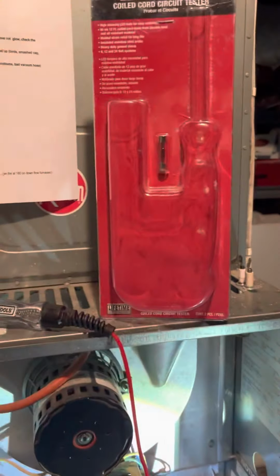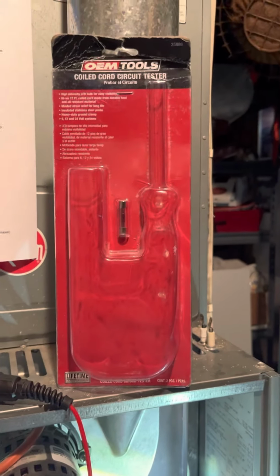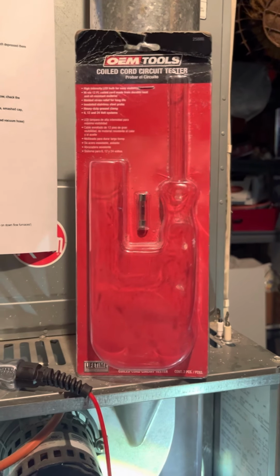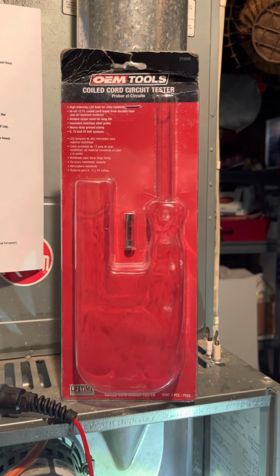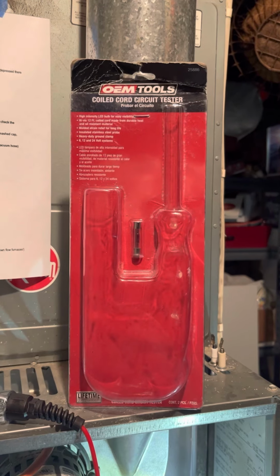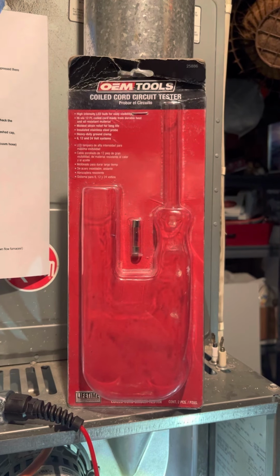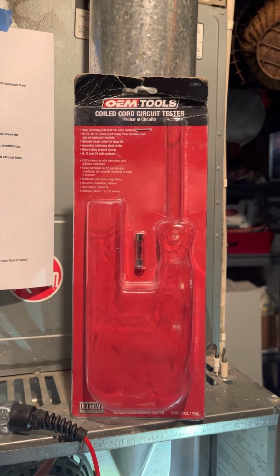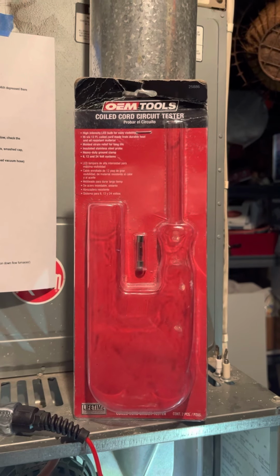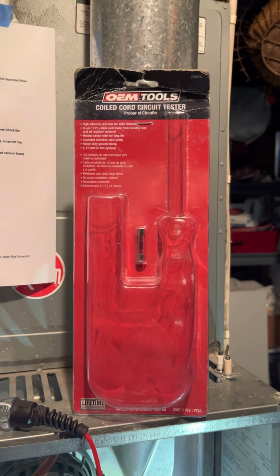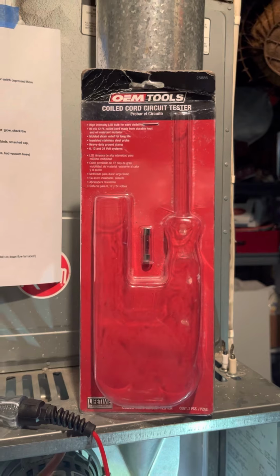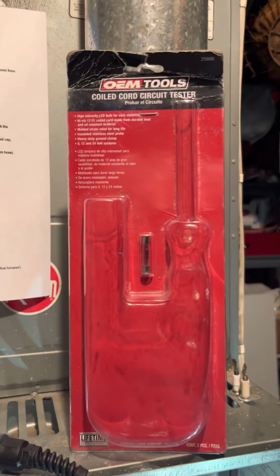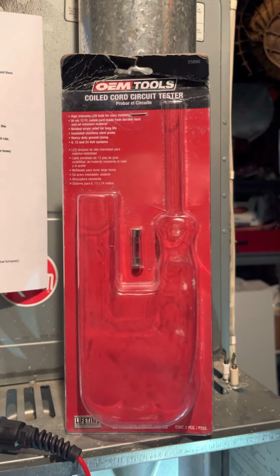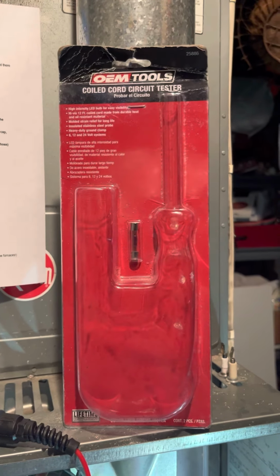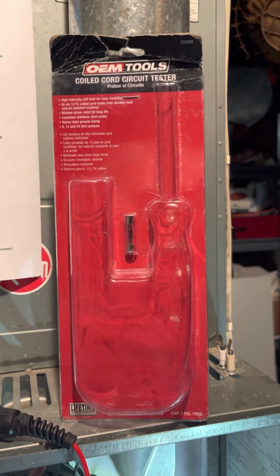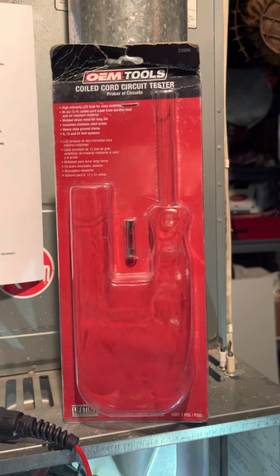Hey guys, I wanted to show you a little trick I use to troubleshoot furnaces. It's a 24 volt test light, and what that does is it'll tell me at what point in the sequence of operation the furnace stops operating, and you can test it rather quickly and get to the problem, then pull out your multimeter and do some more extensive testing.